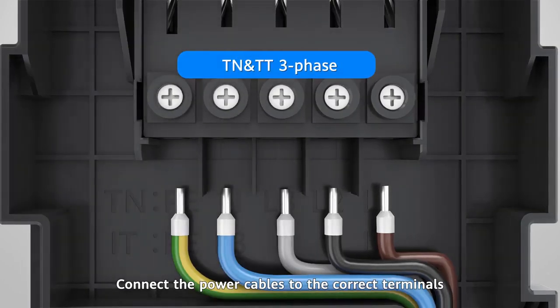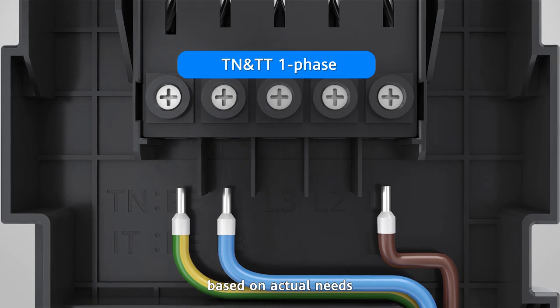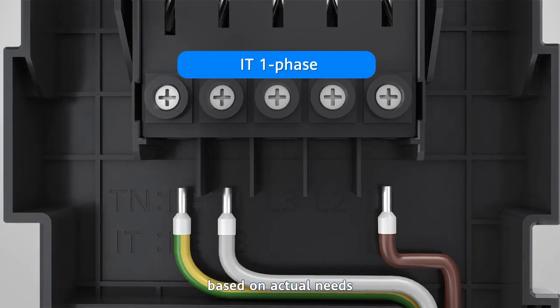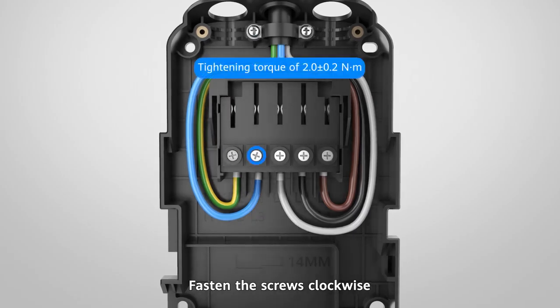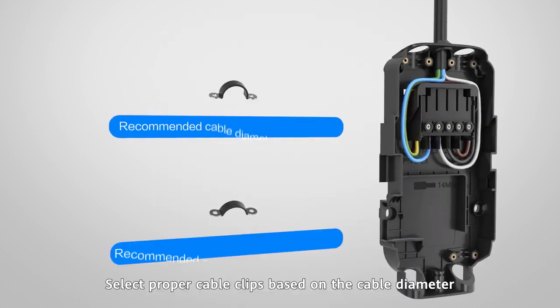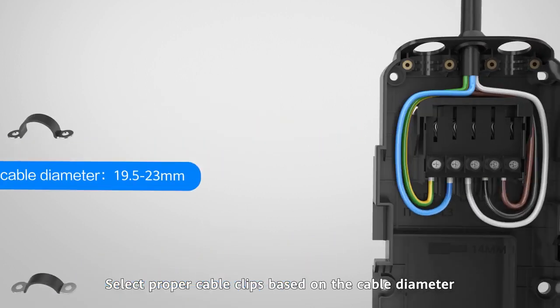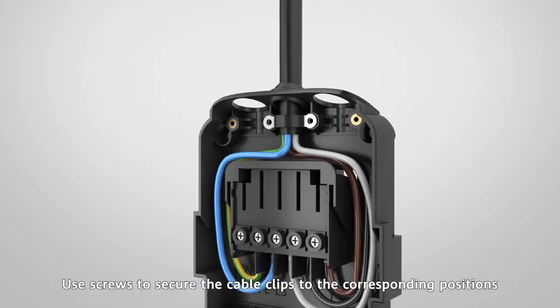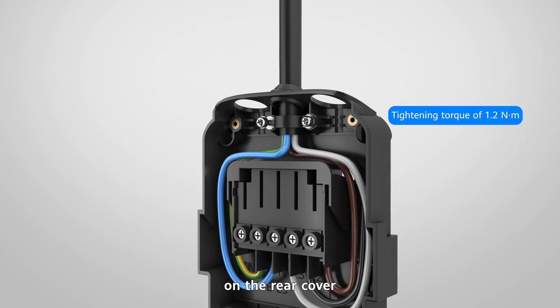Connect the power cables to the correct terminals based on actual needs. Fasten the screws clockwise. Select the proper cable clips based on the cable diameter. Use screws to secure the cable clips to the corresponding positions on the rear cover.